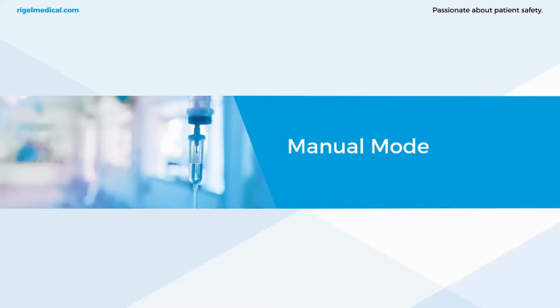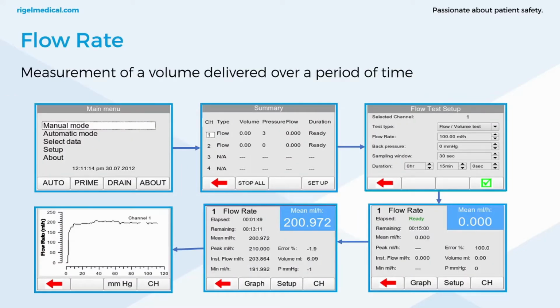Case of manual mode using the Multi-Flo. Measurement of the volume delivered over a period of time. This is how we carry out the flow rate test. So we go to test, manual mode. We're in here, we select the green encoder button, so we're on 1 if we're using the first channel. And then we can change all our parameters within the flow test setup. So once we're happy with our parameters, we select this function key here, and then we're ready to test. You press the green button again on the Multi-Flo, and then it's ready to measure.